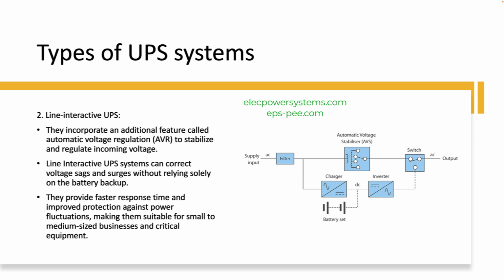Line Interactive UPS. Line Interactive UPS systems offer enhanced protection compared to standby UPS systems. They incorporate an additional feature called Automatic Voltage Regulation, AVR, to stabilize and regulate incoming voltage. Line Interactive UPS systems can correct voltage sags and surges without relying solely on the battery backup. They provide faster response time and improved protection against power fluctuations, making them suitable for small to medium-sized businesses and critical equipment.